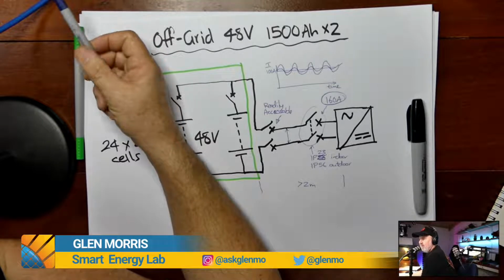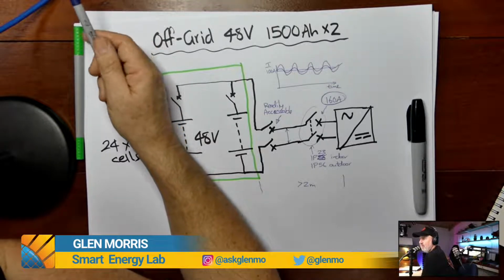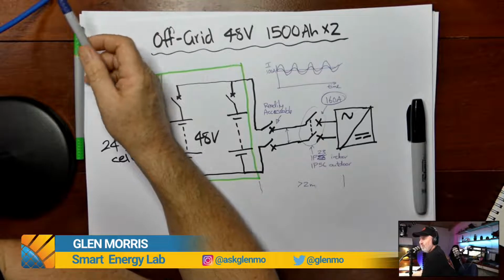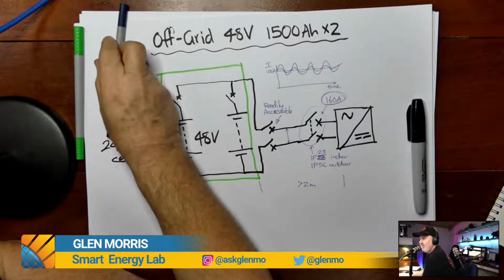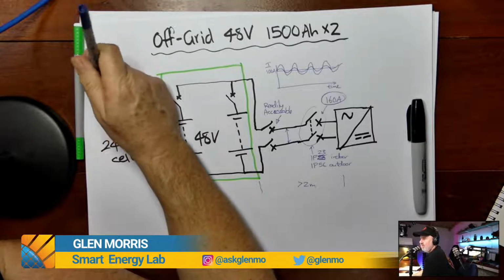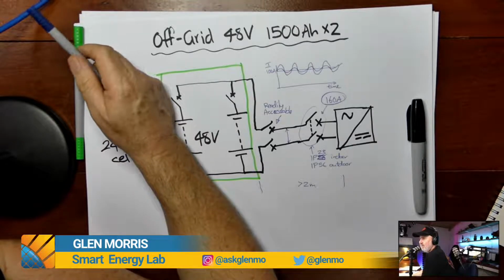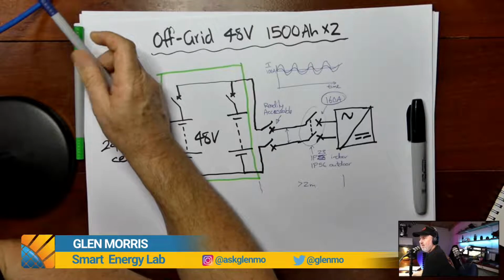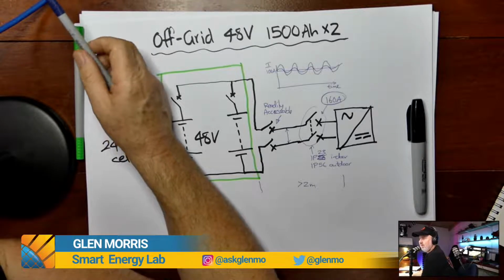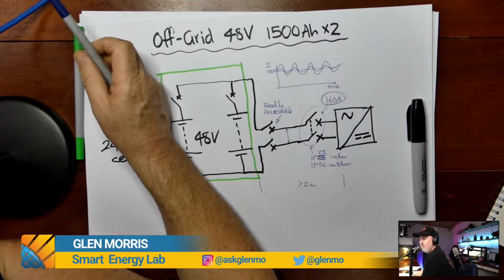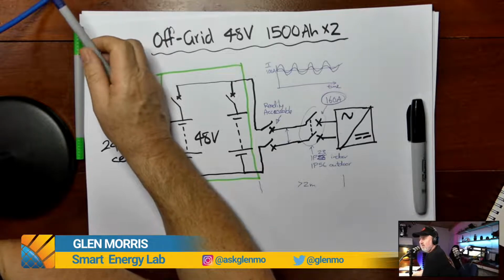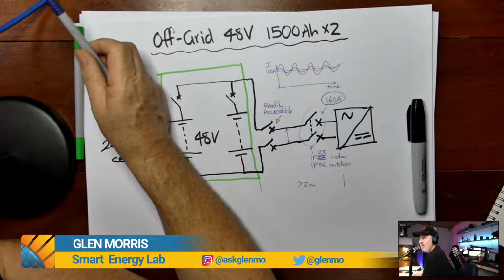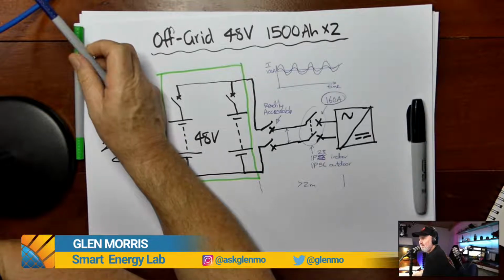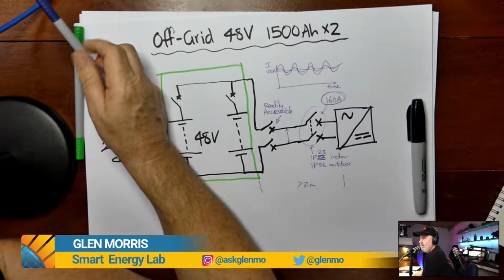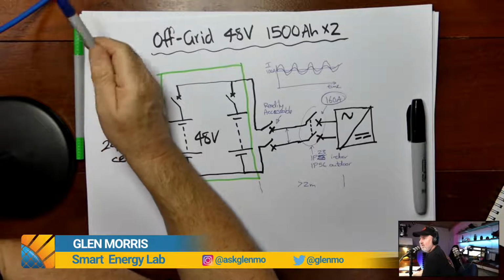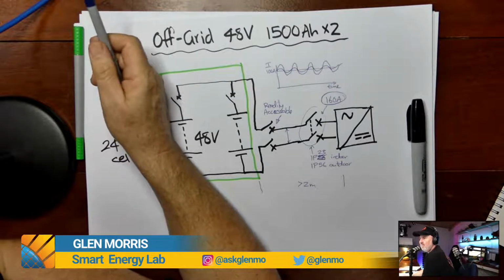So I'd say yes, it can be considered readily accessible, but it's marginal in terms of whether someone would actually work out how to do it in a hurry. So I guess it's a case of a risk assessment on the system operator. I mean, after all, it is there for a purpose. If something goes horribly wrong and you need to turn off the source, you don't want them to have to be going looking for the manual and trying to work it out. So I'd probably encourage having separate isolation, but it's not mandatory. It's probably just good design. So thanks for that one, Anne. Sorry to give you a yes and no answer to that.